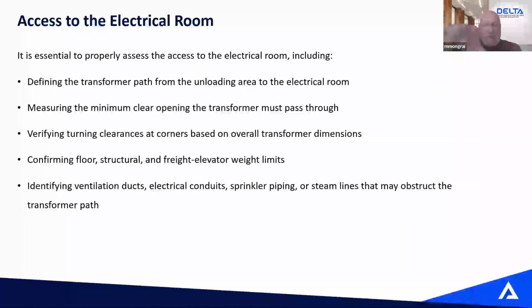We need to walk that path and measure the smallest opening which the transformer must go through, to make sure that we design something that will pass through. We've got to make sure about all the turning clearances, and always, if you have corridors and you have a 90-degree turn, we need to make sure that it's going to turn there.